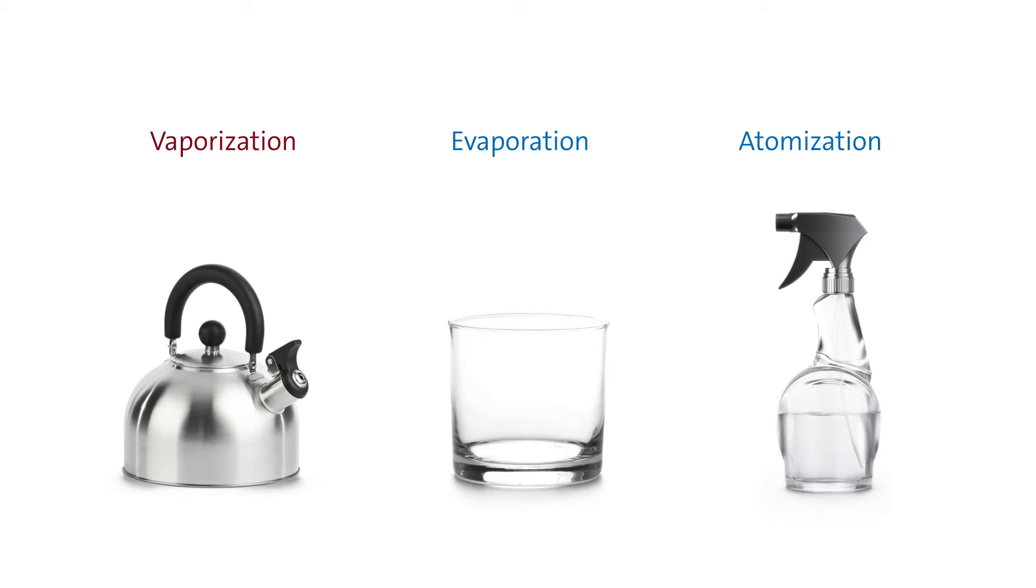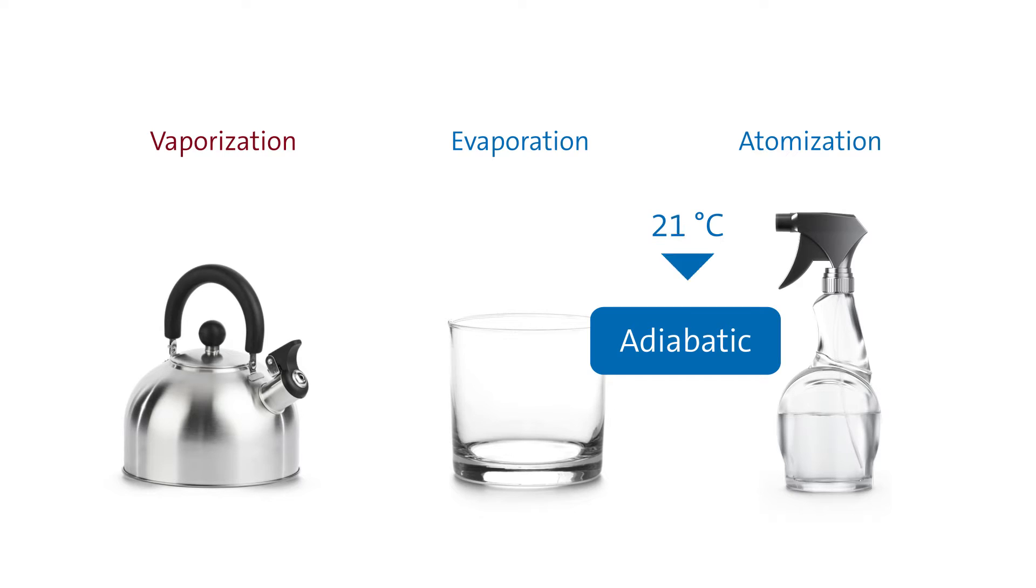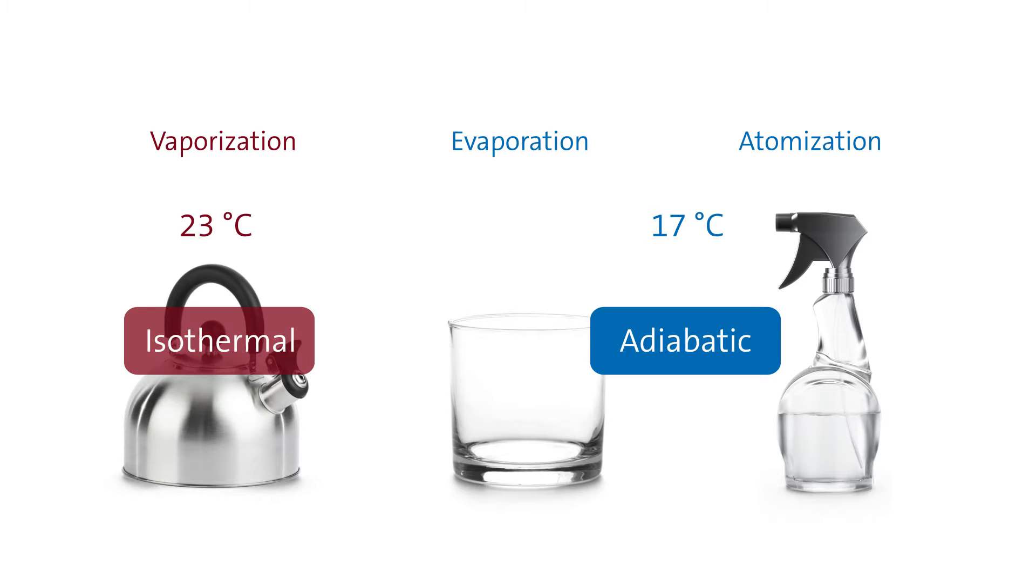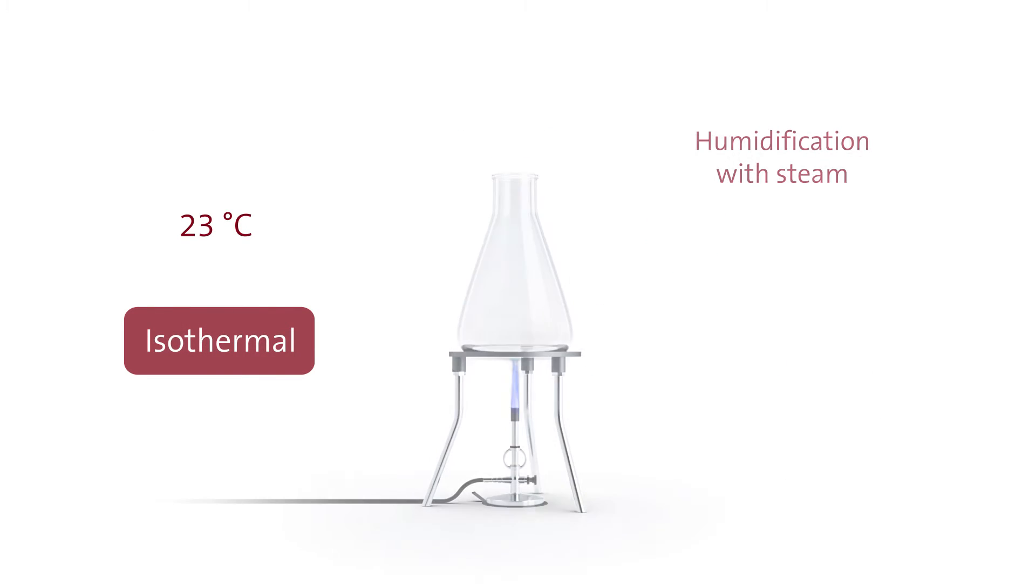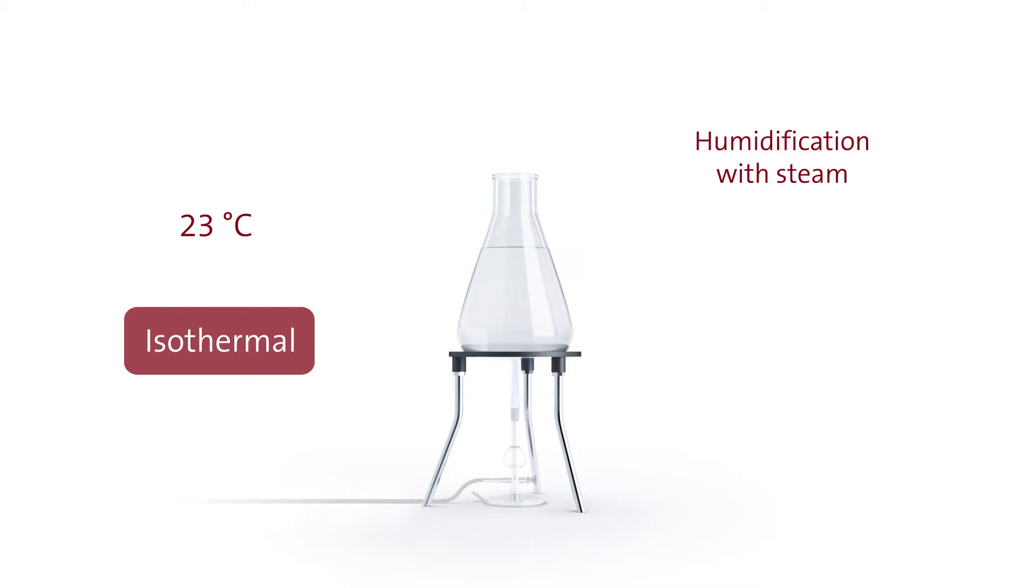The essential difference between these methods lies in the fact that air in adiabatic methods is cooled down. However, the air temperature remains constant with steam humidification. To be exact, steam needs no extra energy to enter into the gaseous state, since it already is gaseous.